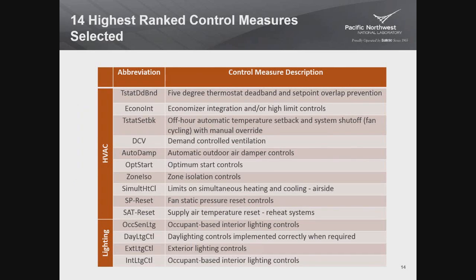I'm going to very briefly discuss these just so that you have a flavor of what they're all about. The first one is 5-degree thermostat deadband and set point overlap prevention. That's a requirement that says that the heating and cooling set points on the thermostat have to be at least 5 degrees apart, so it's not fighting itself in heating and cooling. Economizer integration is the next one. That's a requirement when you need to have an economizer for free cooling when the conditions are right outside. It has to be integrated with the mechanical cooling system. It can't just be one or the other. You have to use both when there's a capability of saving energy to do that.